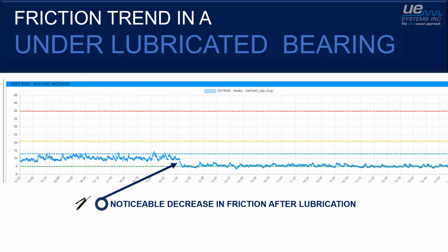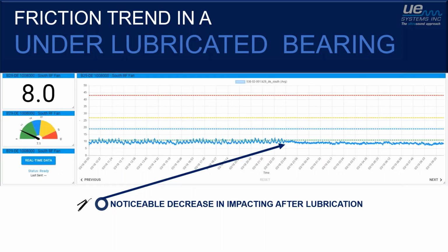All of a sudden, all the theory about friction and viscosity and all that kind of stuff is starting to become visualized. You can see what happens when the correct grease, of course, gets entered into the bearing. Now, this is a great example. This bearing did require lubrication.